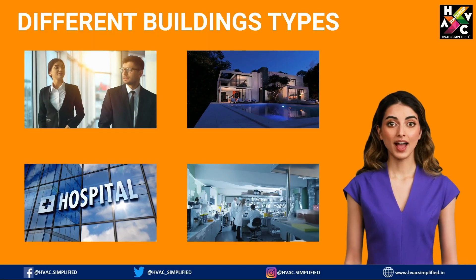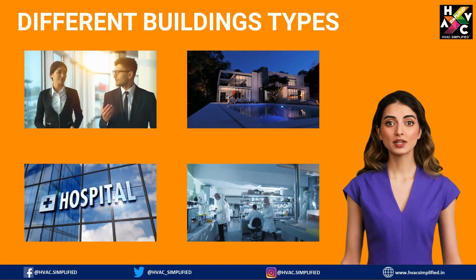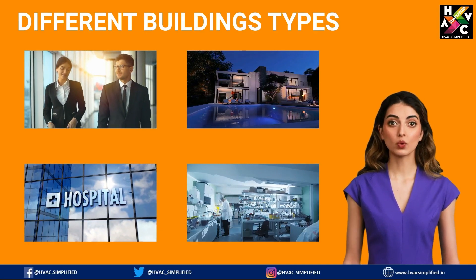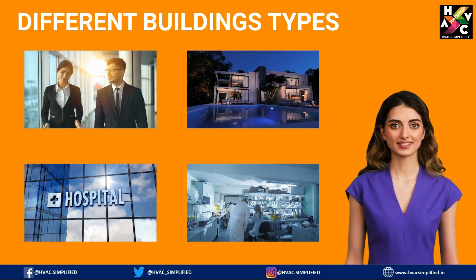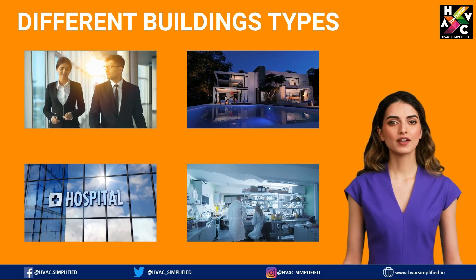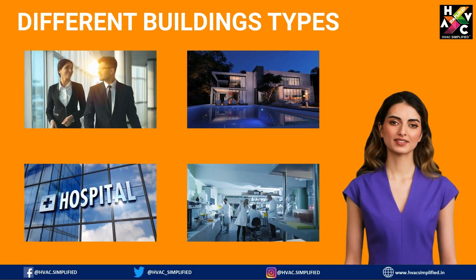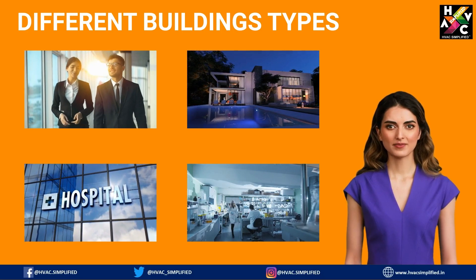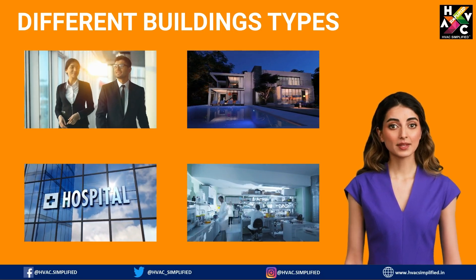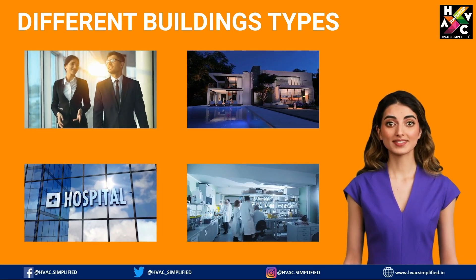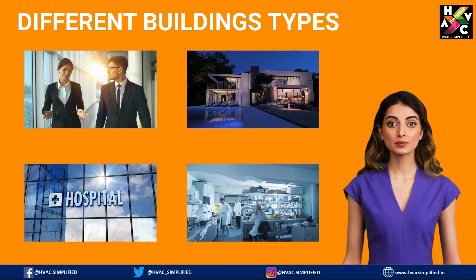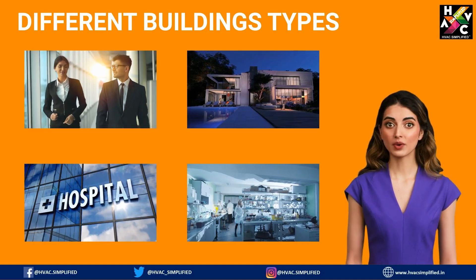Air changes per hour is especially important in spaces with strict air quality requirements, like hospitals, labs or industrial facilities. Residential and commercial buildings have different ACPH recommendations based on their function. For example, a typical office might need four to six air changes per hour, while a hospital operating room could require 15 or more.